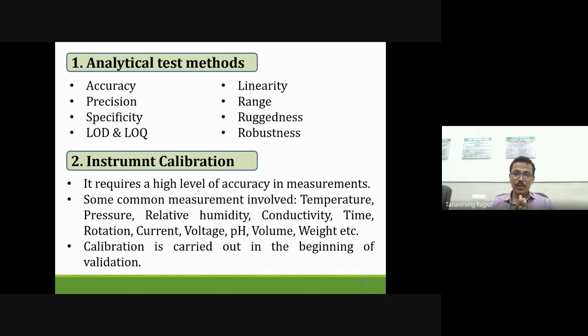When we discuss qualification, qualification is whatever processes we have carried out for calibrating that instrument, or during the installation of that instrument, and all the documented evidence is nothing but the qualification. And validation is all the supporting data or proofs regarding that process, from the instrument calibration to whatever output we get from that instrument.